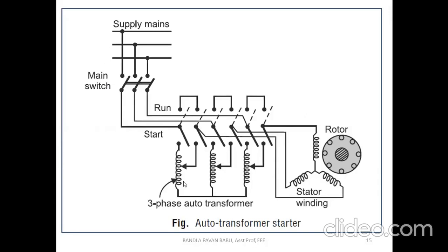With the help of the auto transformer, we are going to give a certain percentage, that is, 50% or 20% tapping or 80% tapping or 75% tapping, likewise. Initially we fix the tapping and start the machine. With the help of this changeover switch, we give the start position. Soon after the machine reaches rated parameters, we use this changeover switch to tap to the run position. Run position means the supply is given directly to the machine. There is no control of any voltage there.